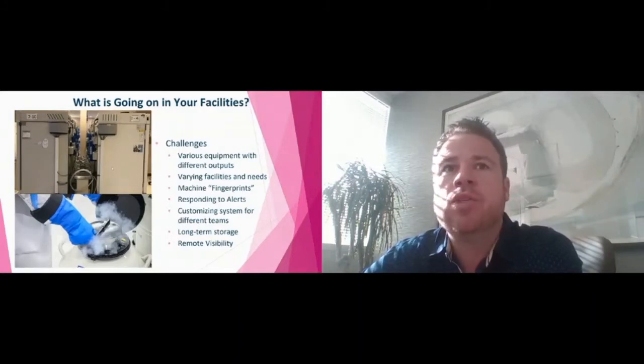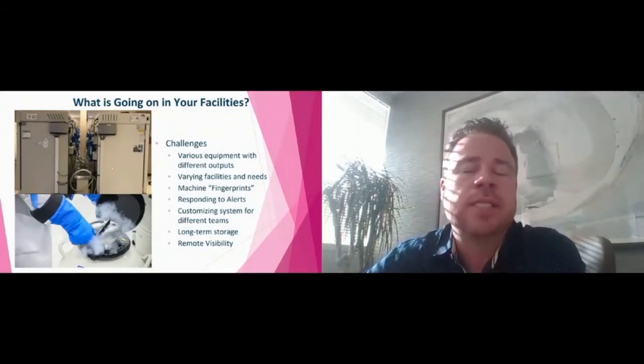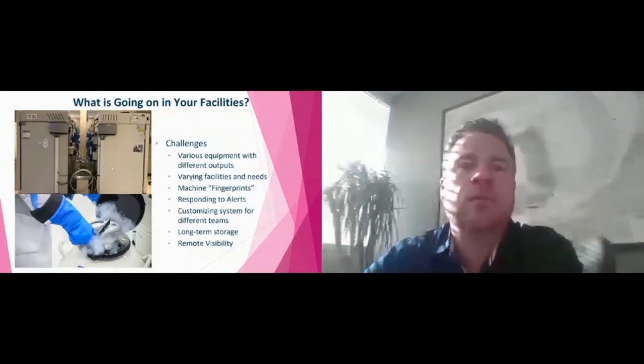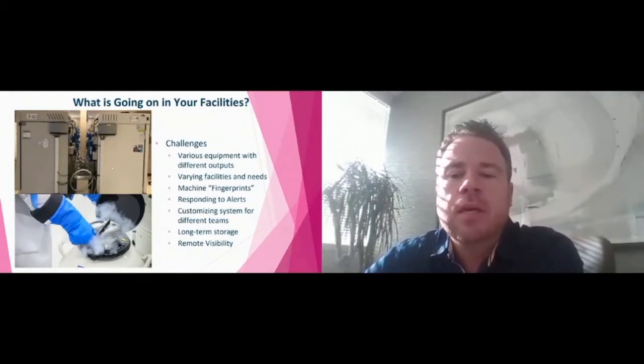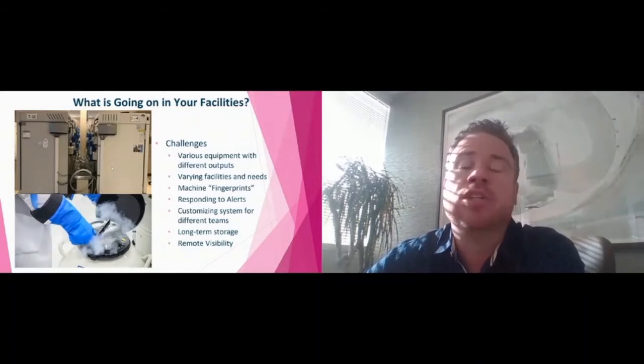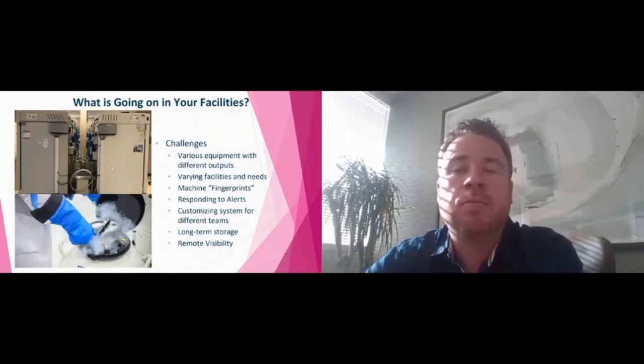In the past, we used to track an incubator spot check twice a day or once a day, and if it wasn't right, we would check in the afternoon. And you would go 3 days, and if you felt that the spot checks that were happening basically at the same time every day were off, you would go ahead and calibrate. Now, with those fingerprints that you're looking at, you can now make more educated decisions on if you need to calibrate or if you need to retire the machine and you're just not happy with the way that it's performing compared to its neighbors.